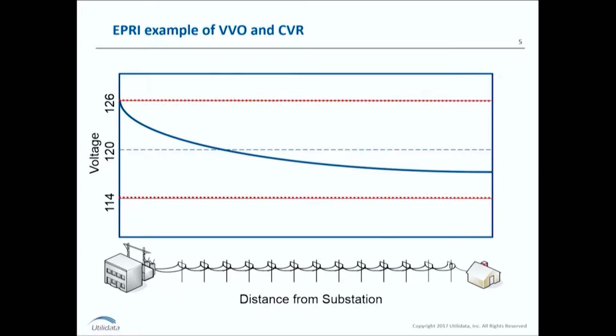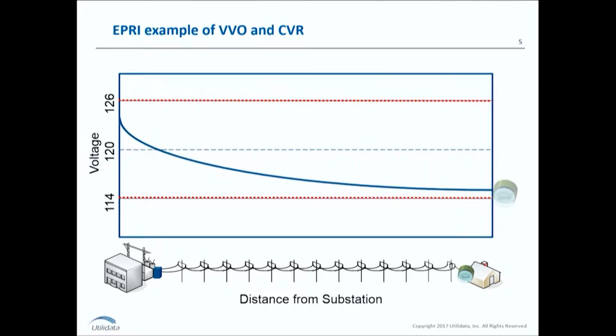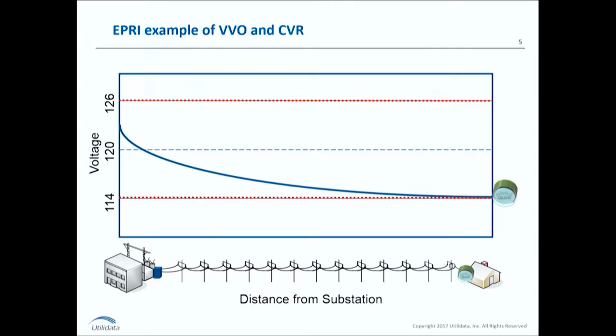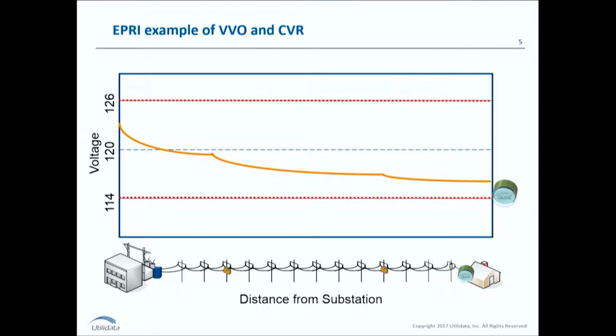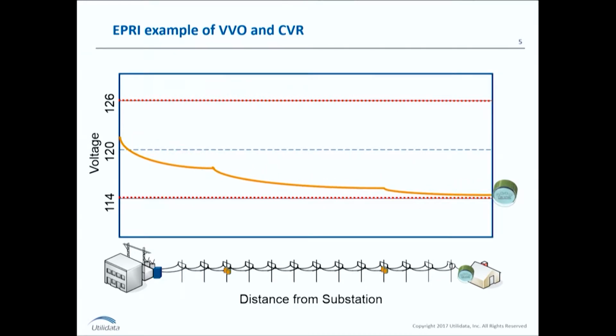EPRI has a great animation showing how the flattening and lowering of the curves are interrelated—two sides of the same coin. This blue line represents voltage losses. As we add a meter at the end of the line, we get information that allows us to lower voltage—that's CVR. Now introduce these two orange capacitor banks, which inject reactive power and further flatten the curve, minimizing line losses. Then we can perform CVR again and lower it further.